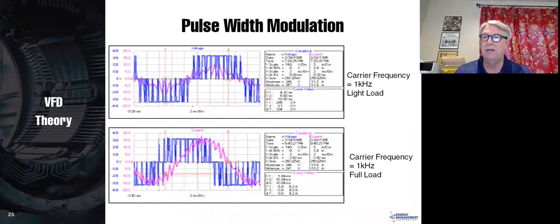Now I've selected a carrier frequency of 1 kilohertz. I have seen, at least years ago, some drives that did not let you select the carrier frequency, but I would dare say that pretty much any drive any of you have, that carrier frequency comes programmed from the factory at a certain value, but you can change that, you can program that. So I selected a carrier frequency of 1 kilohertz. Remember, this is a real variable frequency drive and an oscilloscope tracing. The top graph is at no load, the bottom graph is at full load.